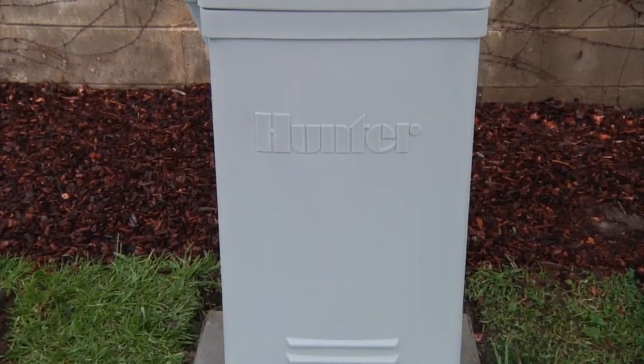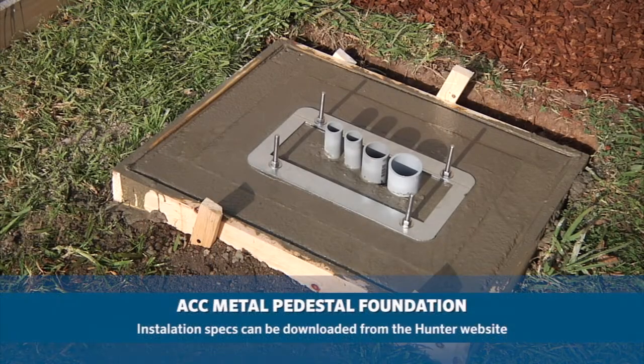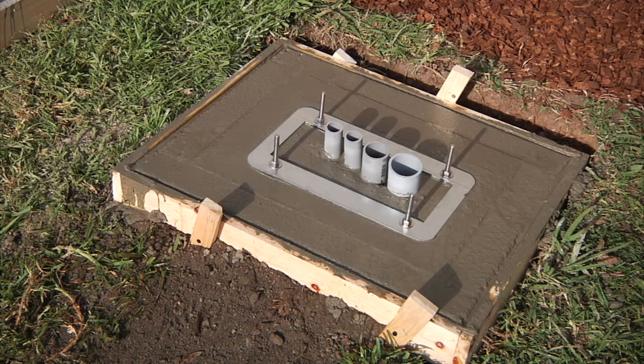To install the plastic pedestal, you'll perform the same steps we already showed you in the metal pedestal concrete base installation. But this time build a form for a 21-inch wide by 26-inch wide concrete base. This is a 53 by 66 centimeter base. Again, set the form using 2x4s or 1x3s and make sure the base pad is 2 inches or 50 millimeters above grade. So we finished the installation of our ACC 99D plastic pedestal controller.